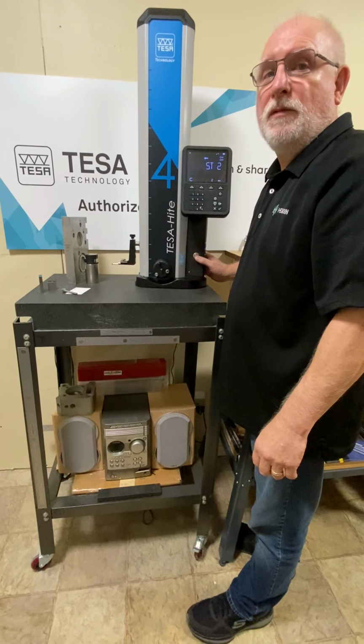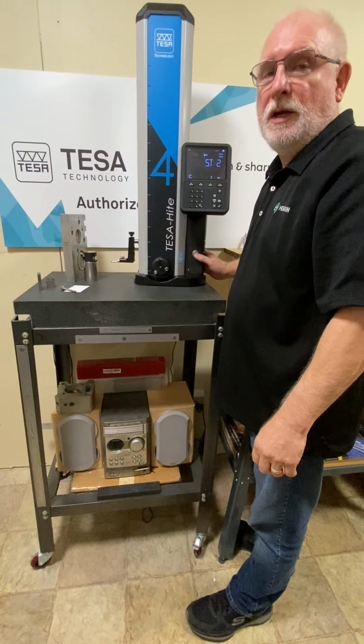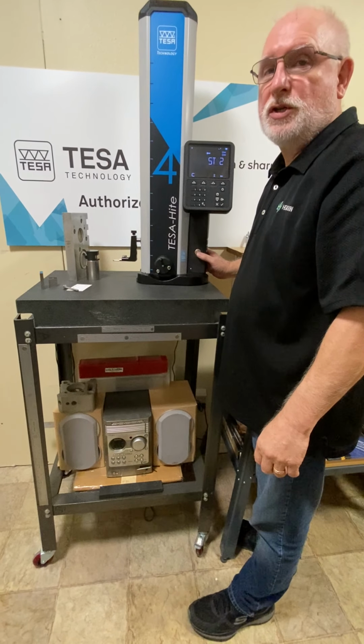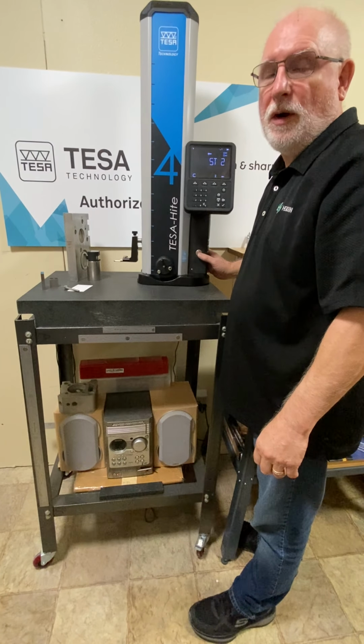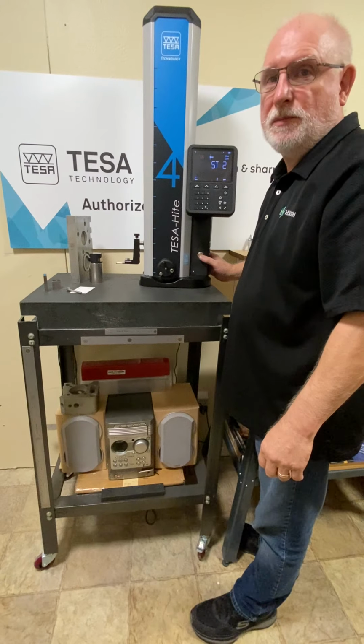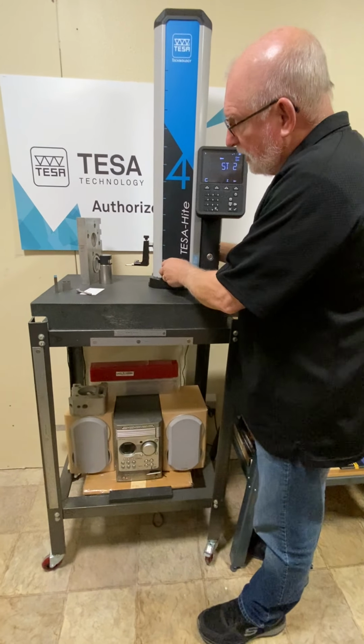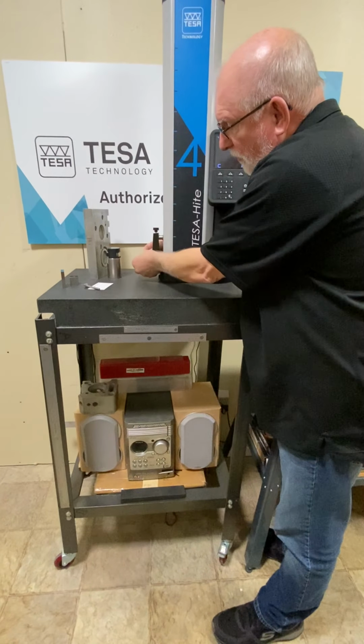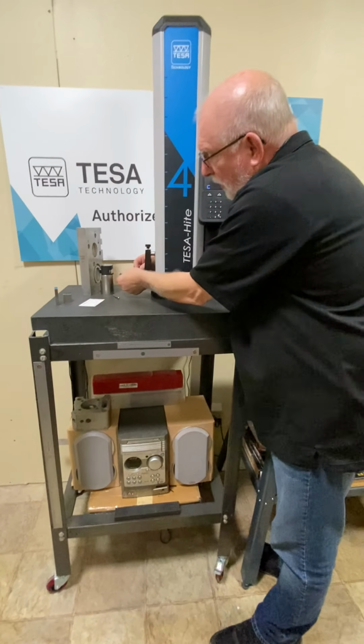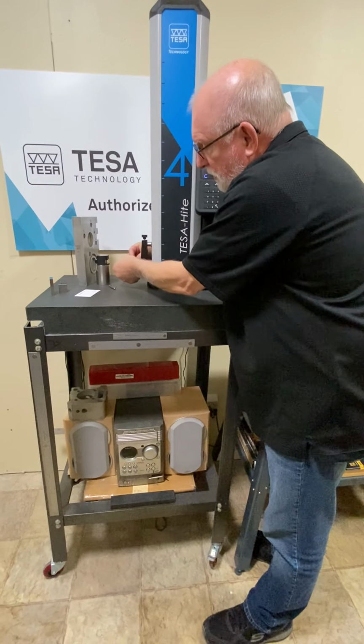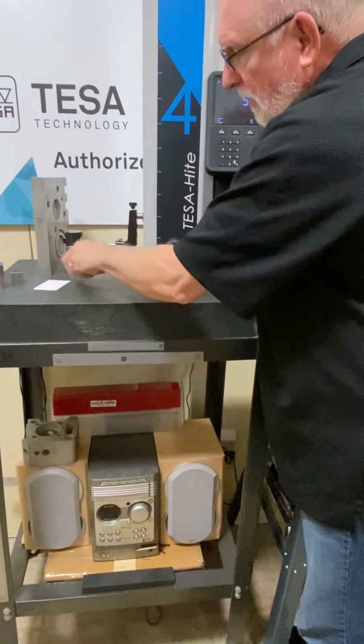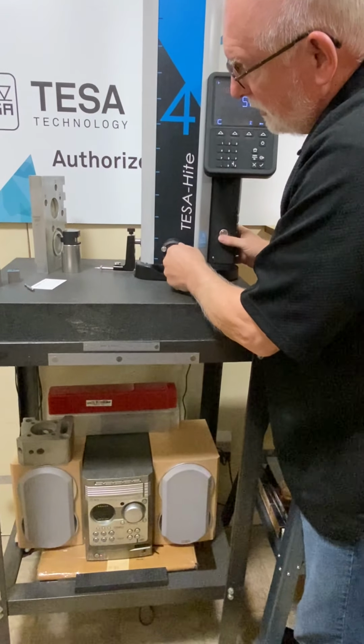I'm going to go over level 2 training on the TESA-Hite. The 3 procedures I'm going to go over are changing a probe, doing an offset, and measuring parallelism. To begin with, I'm going to change out the standard probe that's on the TESA-Hite right now, and I'm going to put in a probe that will not touch the surface plate. So as you can see, it doesn't touch the surface plate.